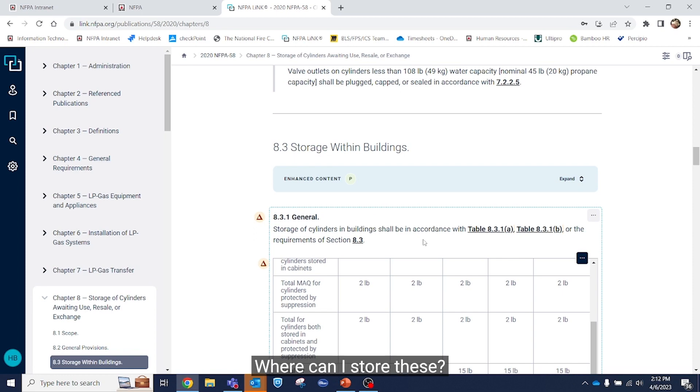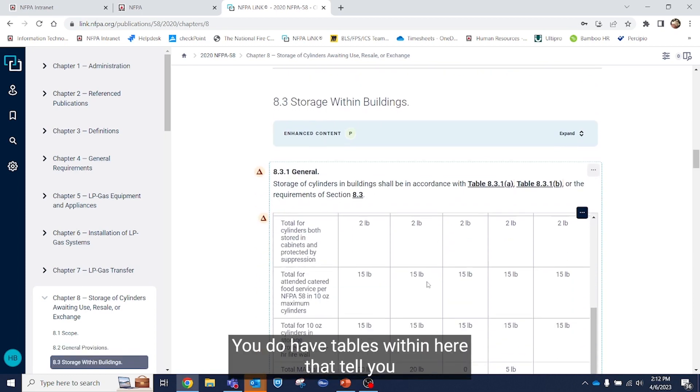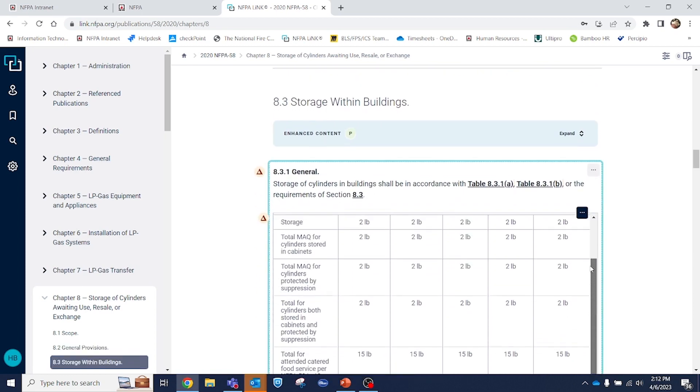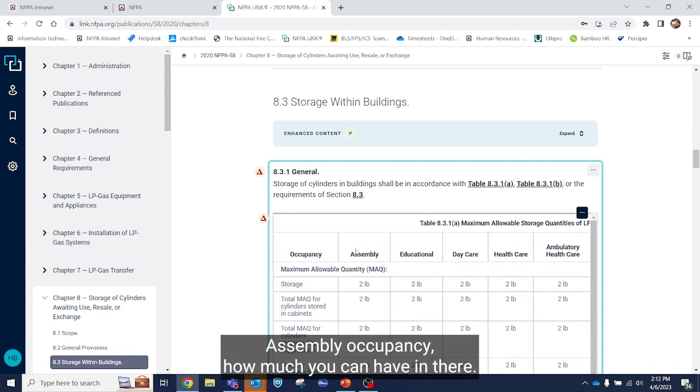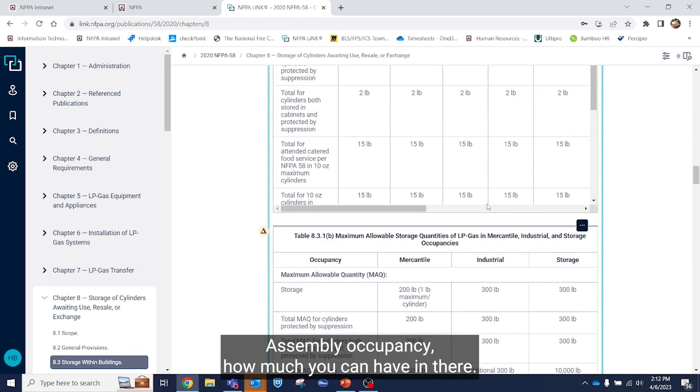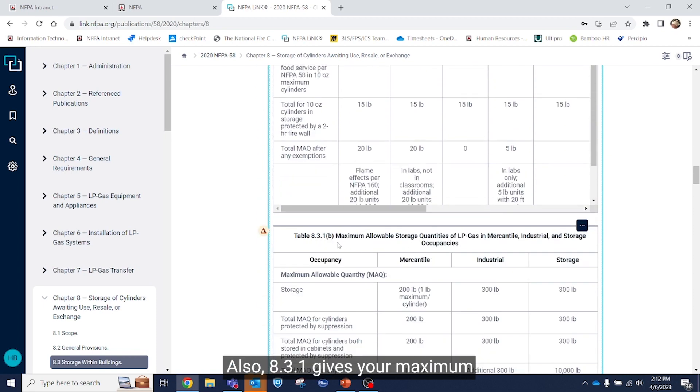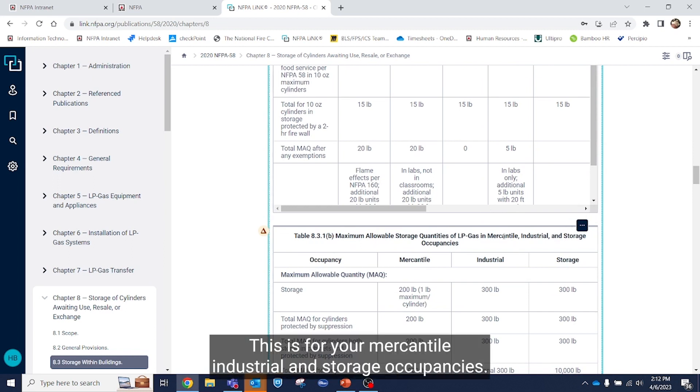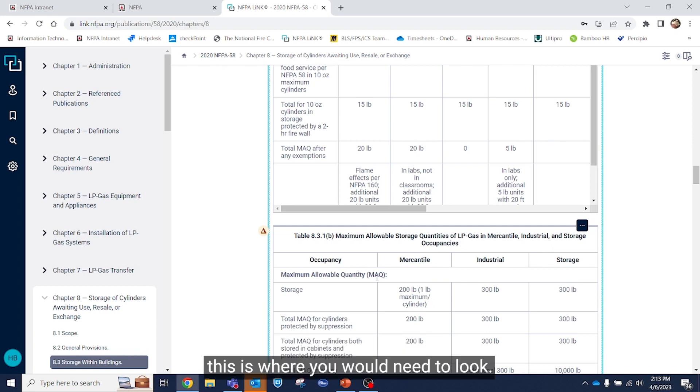Where can I store these? You do have tables within here that tell you your sizes, assembly, occupancy, how much you can have in there. Also 8.3.1 gives your maximum allowable storage quantities. This is for your mercantile industrial and storage occupancies. So if you have storage in an industrial setting, this is where you would need to look.